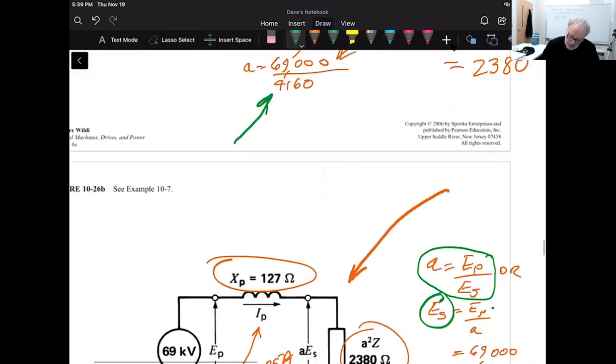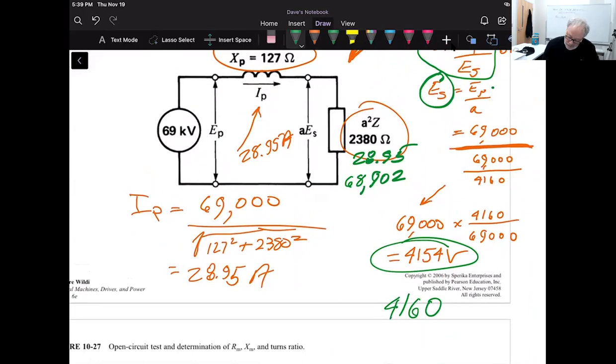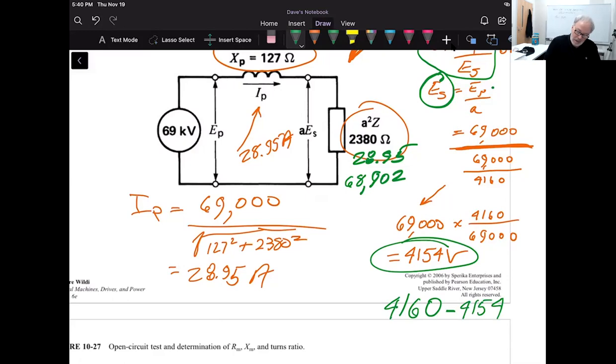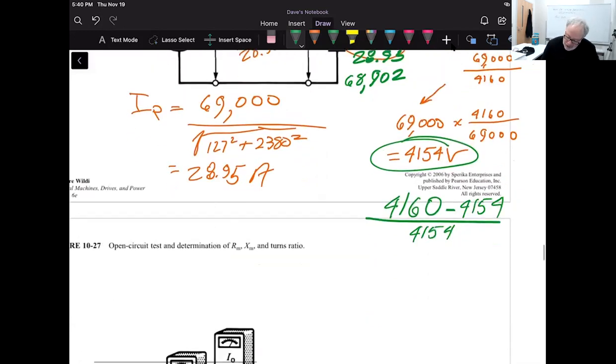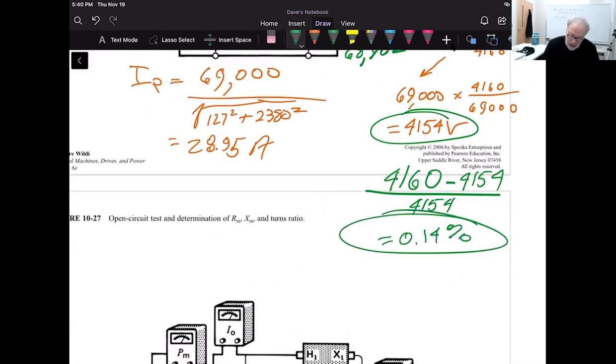Since the primary voltage is held constant at 69,000 V, the secondary no-load voltage is simply the nameplate value of 4,160 V. Applying the voltage regulation formula: (4,160 - 4,154) / 4,154 times 100 gives us 0.14%. That is excellent voltage regulation — less than one percent loss, meaning this transformer maintains its secondary voltage very well under load.